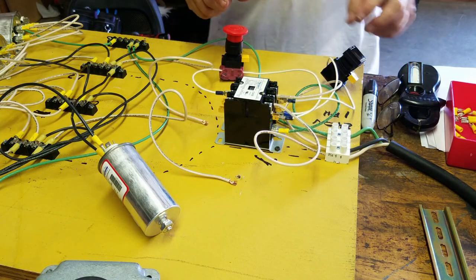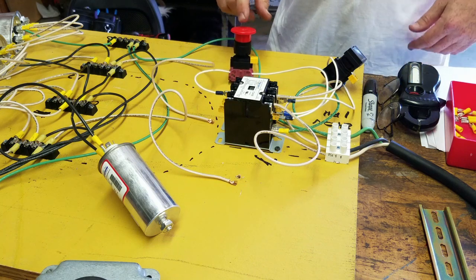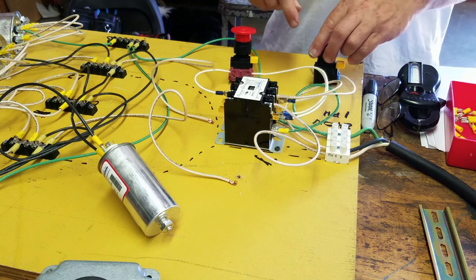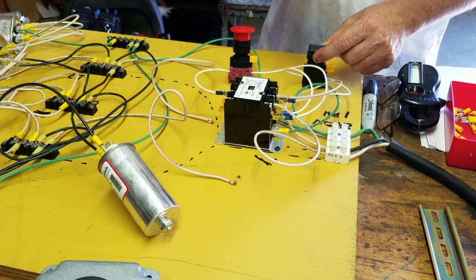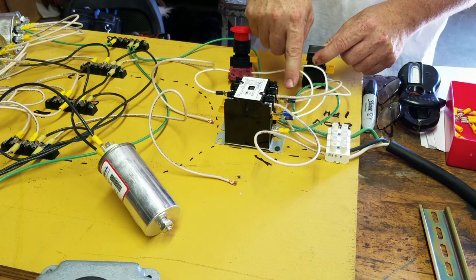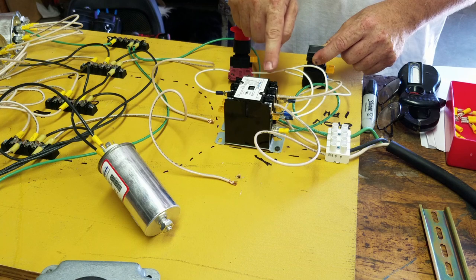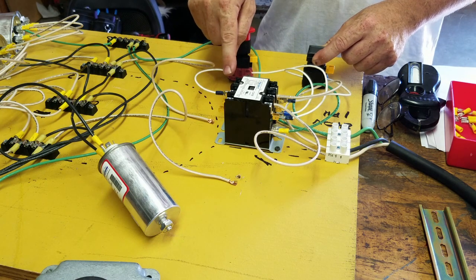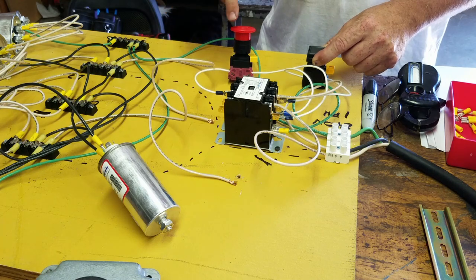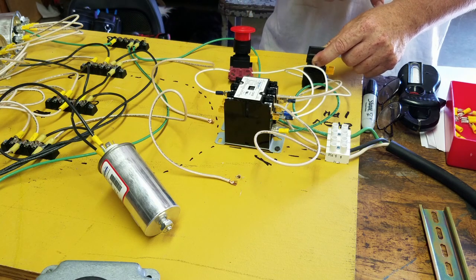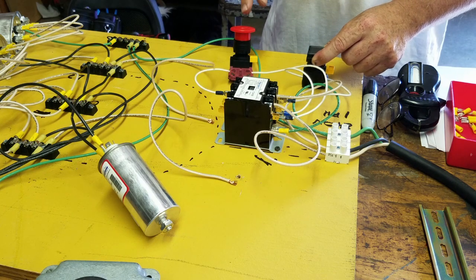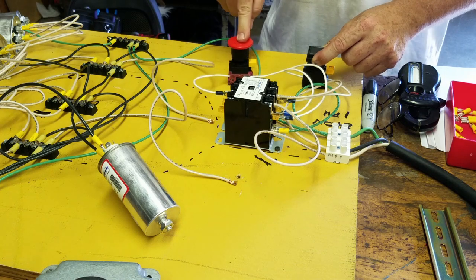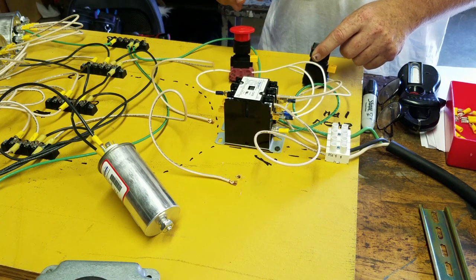So this is a normally open, or normally closed switch. So it's always flowing power. This one's normally open. So let's go through this. When I push the button, I pull power off the line, activate the coil, and I get power going from one side of the relay to the other. Once I get to the other side, I borrow power from it, which keeps going through here, and that energizes the coil continually. Basically, like I said, a self-fulfilling prophecy. When I break this circuit here by pushing the E-stop, the magnet should release. So let's give it a try.